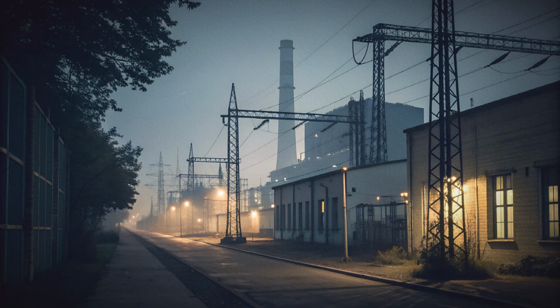Reserve capacity is an important part of operations. Spinning reserve consists of generation capacity that is online and synchronized, but operating below its maximum output. It can increase output almost immediately when needed. Non-spinning reserve refers to capacity that can be brought online within a defined time, such as through starting additional turbines or activating demand-side resources. Reserves are scheduled based on expected demand, historical variability, and uncertainty in supply. When a generator trips offline or when a rapid change in consumption occurs, reserve capacity is dispatched to restore balance.